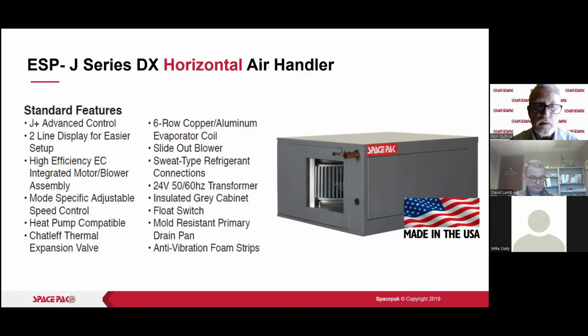6-row copper aluminum coil, slide out blower. It's slide out blower, but I will warn you that the duct has to be removed for that blower to slide out. So just keep that in mind. And insulated gray cabinet. Again, we do have a new cabinet finish, a new metal actually, that will be unfinished because it's not susceptible to rust. We have that coming up.